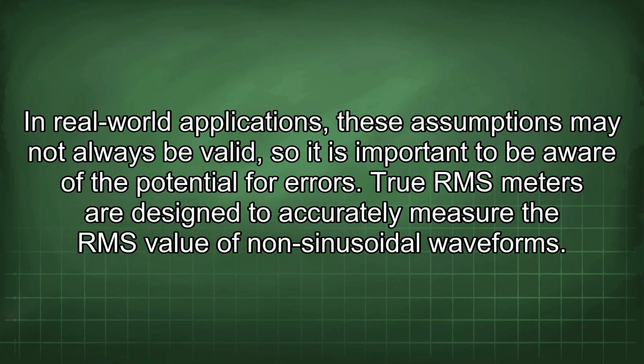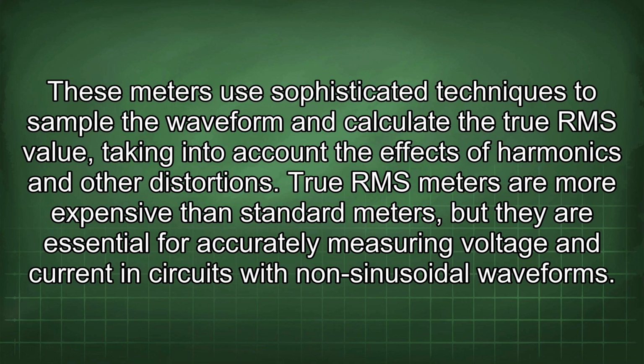In real-world applications, these assumptions may not always be valid, so it is important to be aware of the potential for errors. True RMS meters are designed to accurately measure the RMS value of non-sinusoidal waveforms. These meters use sophisticated techniques to sample the waveform and calculate the true RMS value, taking into account the effects of harmonics and other distortions. True RMS meters are more expensive than standard meters, but they are essential for accurately measuring voltage and current in circuits with non-sinusoidal waveforms.